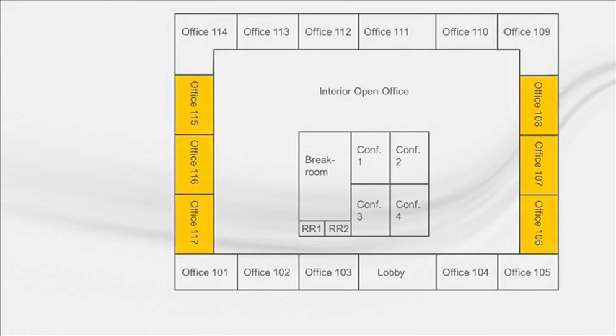The ultimate goal of zoning a heat recovery system would be to equalize the cooling and heating loads on the same heat recovery system. Coupling the east and west offices from the previous example on one heat recovery system will likely result in some savings in simultaneous heating and cooling. However, this requires longer and more extensive refrigerant piping, and as Dave mentioned, can be challenging in terms of compliance with ASHRAE Standard 15. Another possibility is to couple the interior zones and the dedicated outdoor air unit on a single VRF heat recovery system.